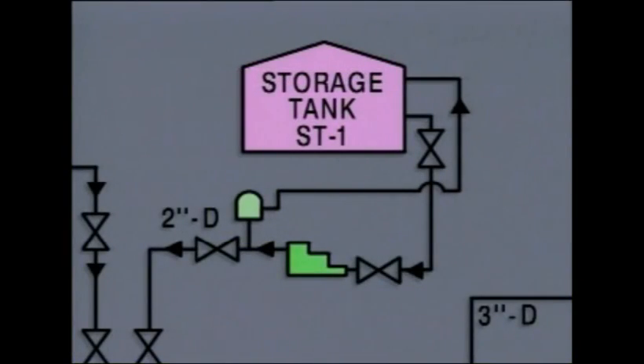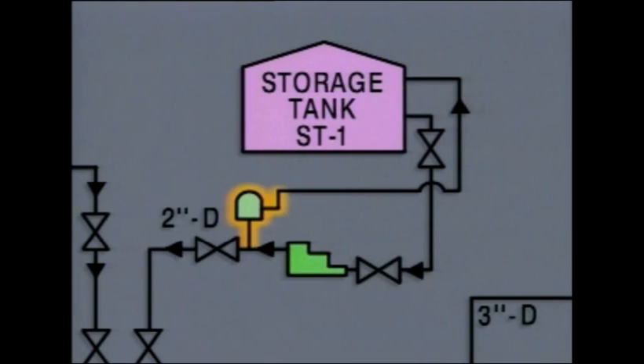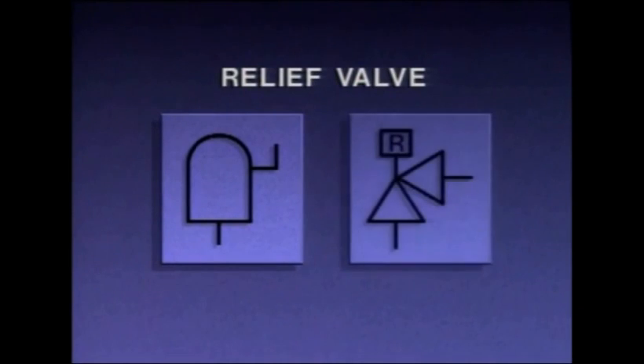The final valve symbol on this diagram represents a relief valve. The relief valve opens when system pressure exceeds a preset limit to vent fluid from the system. If the pressure continues to rise, the valve opens further. Once pressure returns to normal, the valve closes automatically. This is a typical symbol used to represent a relief valve, and you may also see it represented another way.